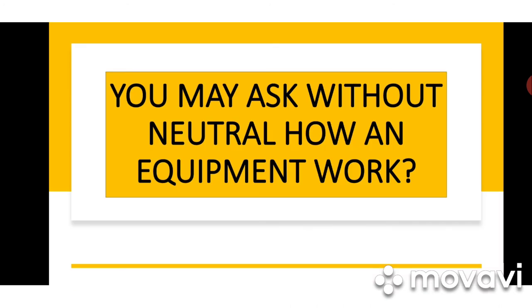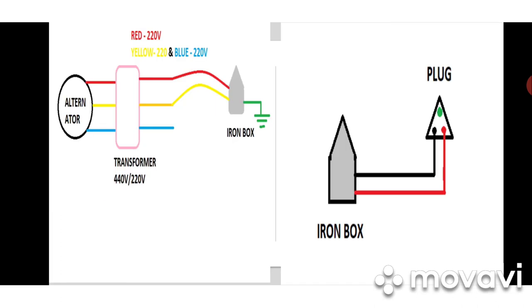Let's see how equipment works without neutral. On the right side there is an iron box getting one phase (red) and one neutral (black). On the left side — the ship side — the alternator produces 440 volts and we use one transformer to step down 440 to 220 volts. From the transformer, 440 volts comes in and is stepped down to 220 volts, and we use two phases — R and Y (red and yellow) — for the equipment, whereas at home we use red and neutral.